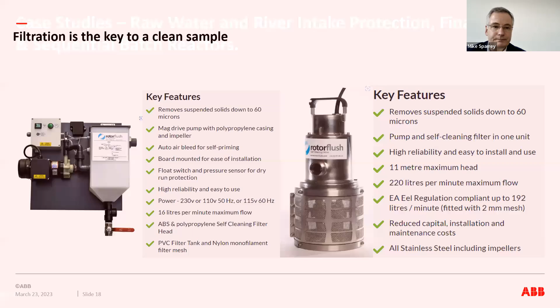If we look at these two, the reason why we've used these products for a number of years is, one, you can see that it removes suspended solids down to 60 microns. Great. Two, it's actually self-cleaning. It takes, like a centrifugal force, takes water in, and then pumps it out and cleans. So you're not having to lift things up or replace things. And the micron pore size, the mesh size, allows us to play depending on the application. So let's have a look at some of the case studies that we do have here.